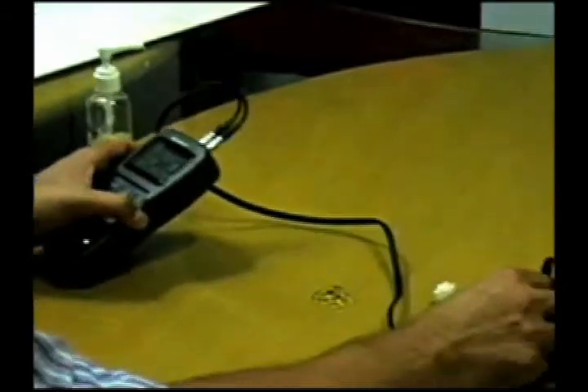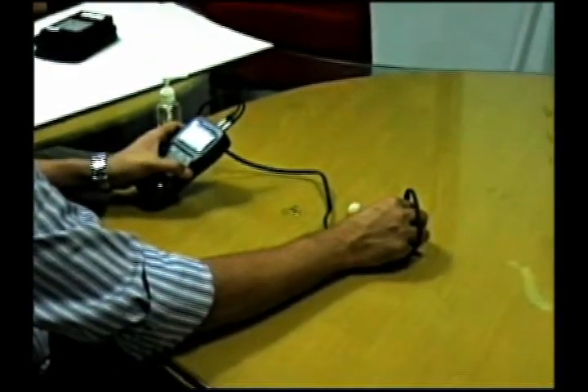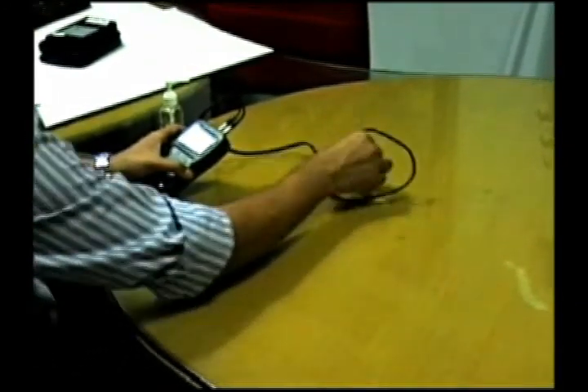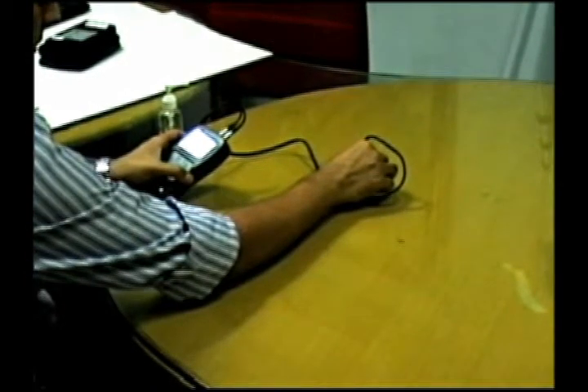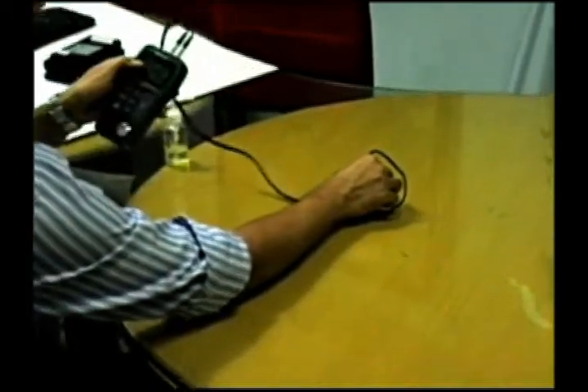Similarly, we can test the thickness at various other locations. For example, here is 12.95 mm, or at another location is 12.98. At all times there is a contact display over here which confirms that the contact of the transducer with the material under test is perfect.